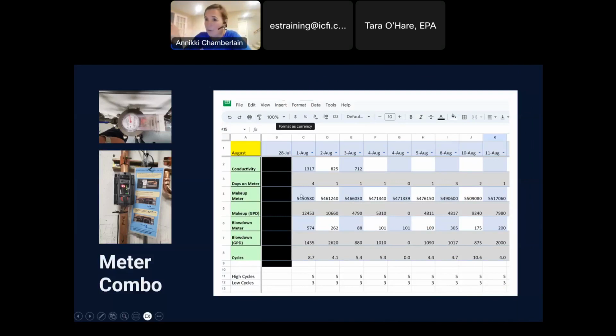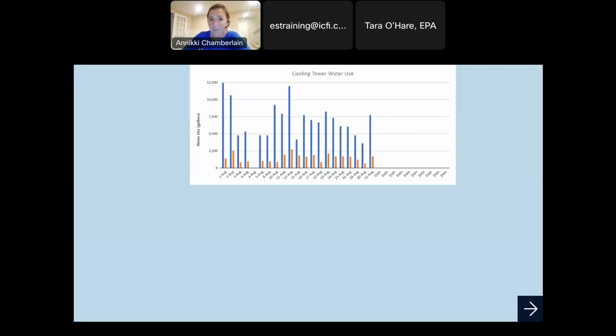But again, I made a form where they just had to select the day and put in the makeup meter read. It would automatically calculate the use since the last one, and then they would enter the blowdown meter reading. So that part of their normal routines just updated the form. So it gives me water use information, which is great. That's what I want. But is that really helpful?